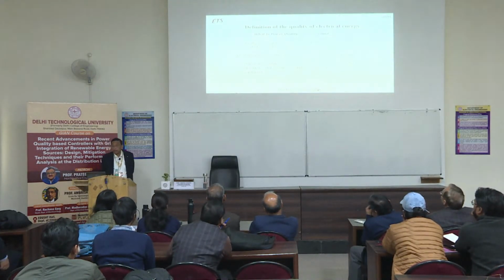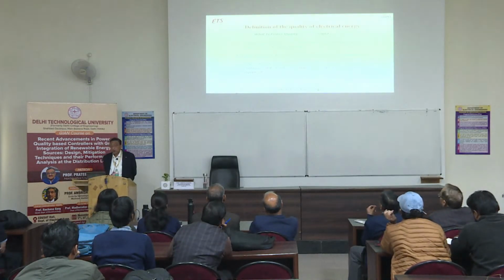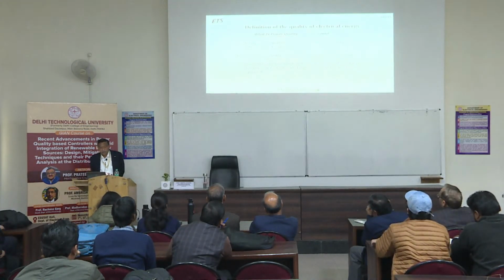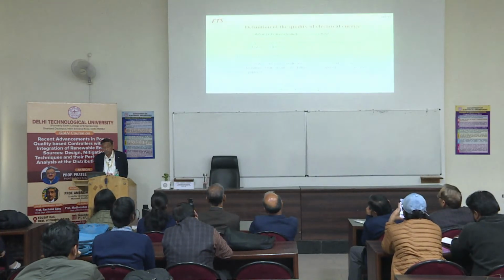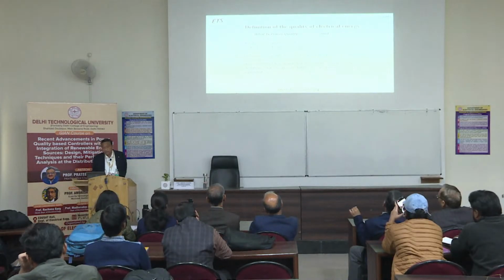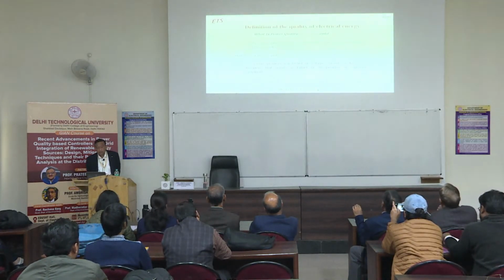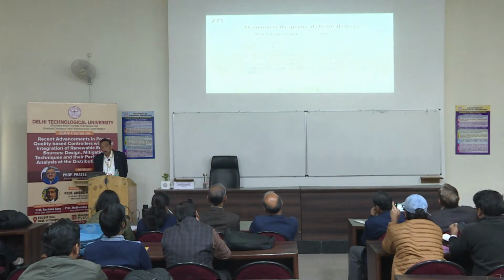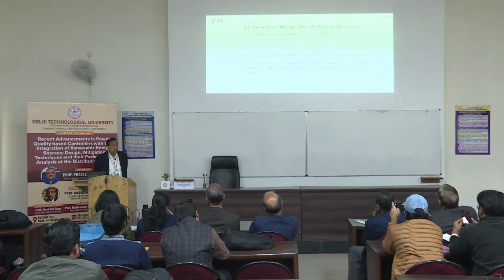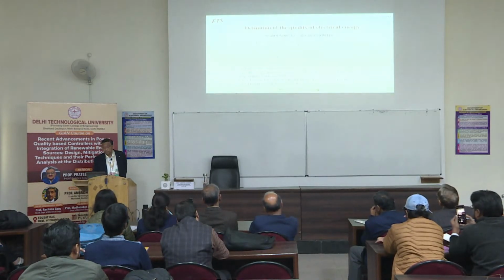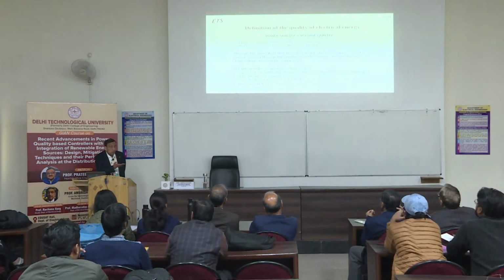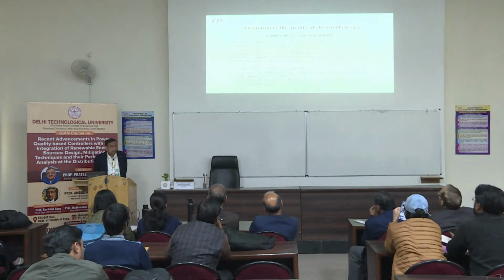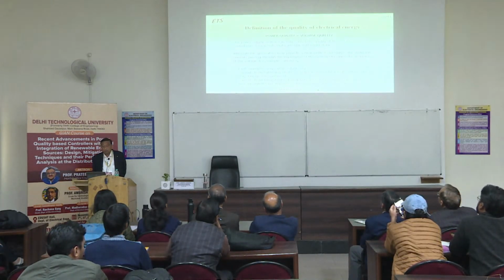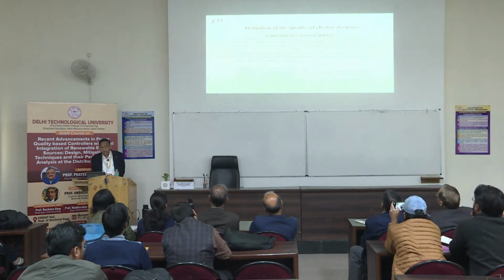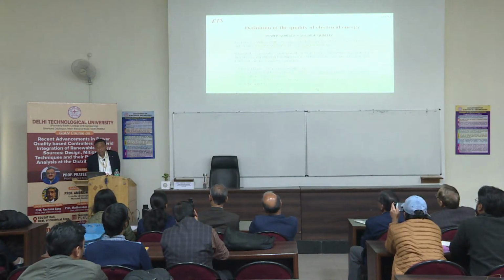Finally, power quality is a customer-driven issue, and the customer's point of view is the most important. Therefore, a power quality problem may be defined the following way: any power problem manifested in voltage, current, or frequency deviations that results in failure or misoperation of customer equipment. There we say there is a power quality problem. Power quality equals voltage quality, as Professor Madhusudan was saying. The power supply system, the utilities, can control the quality of voltage. It has no control over the currents that a particular load might draw.